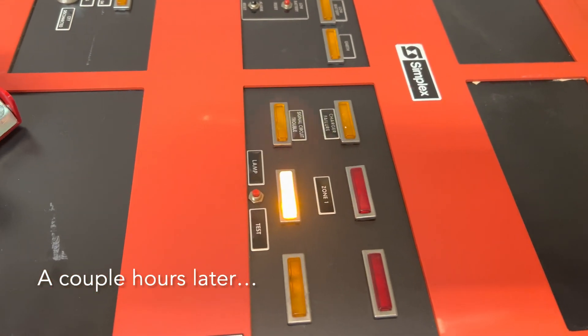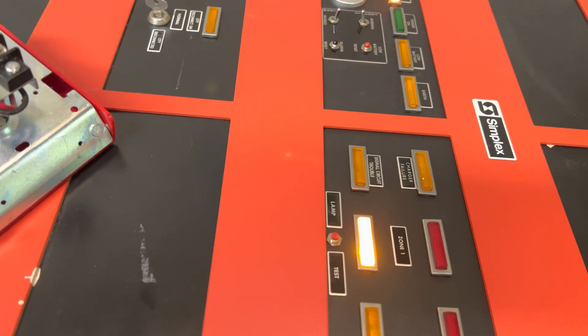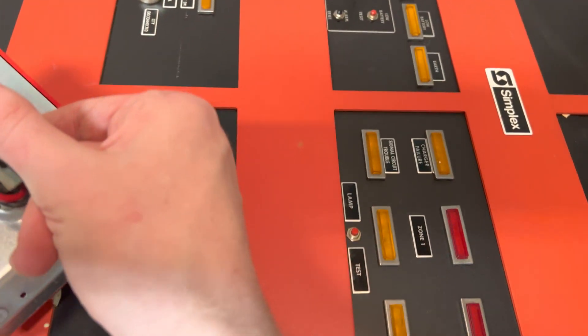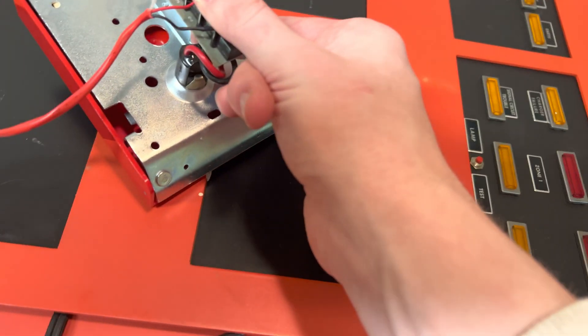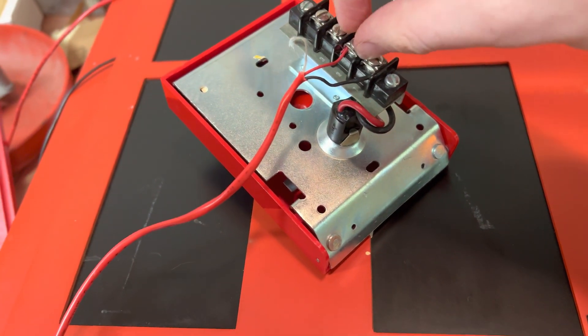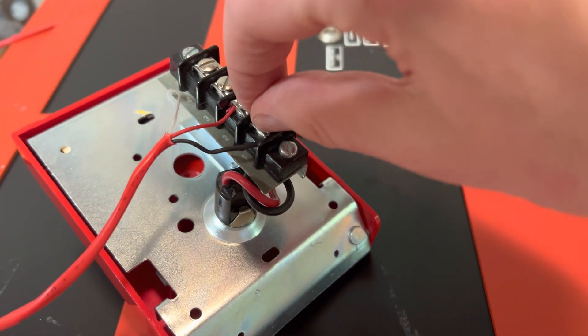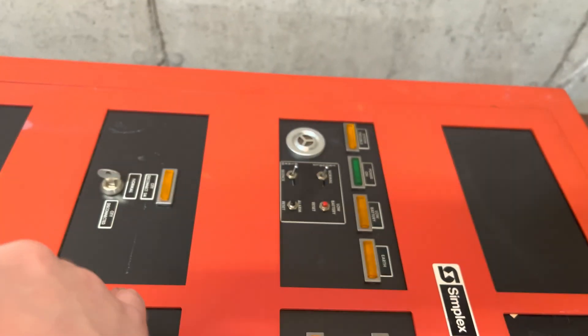The panel only came with enough resistors for one of the zones and also the signal circuit. One thing I noticed when I was working on it — my finger bridged the contacts. And apparently, skin has just the right amount of resistance to make the panel think there's the right resistor there. Just thought I'd share that.